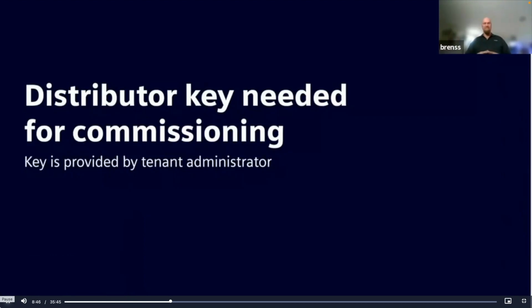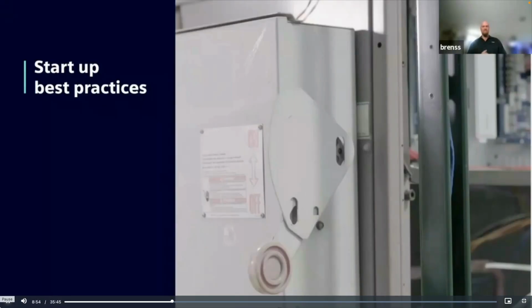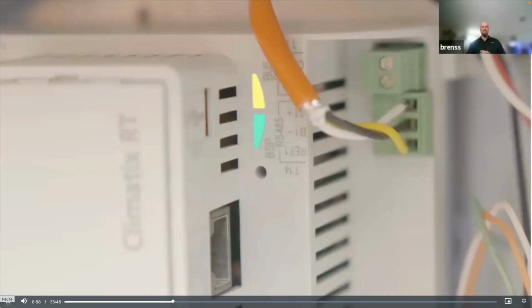Before commissioning, be sure to have your distributor key available. This key is provided by your tenant administrator. Power on the RTU and check that the Climatix RT controller lights are green. On first connection, the connection to the cloud may take a few minutes.